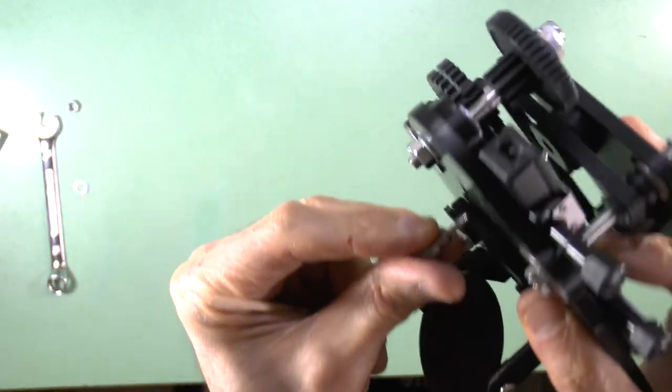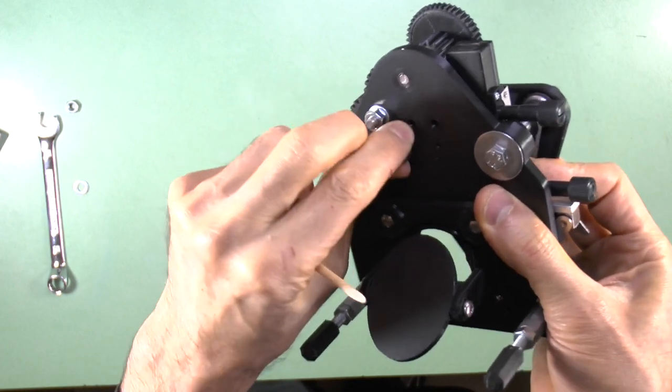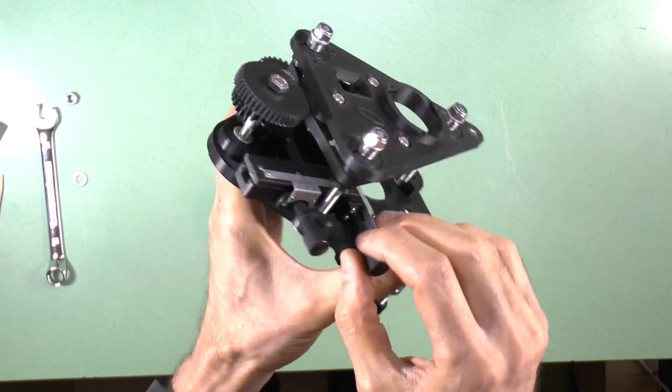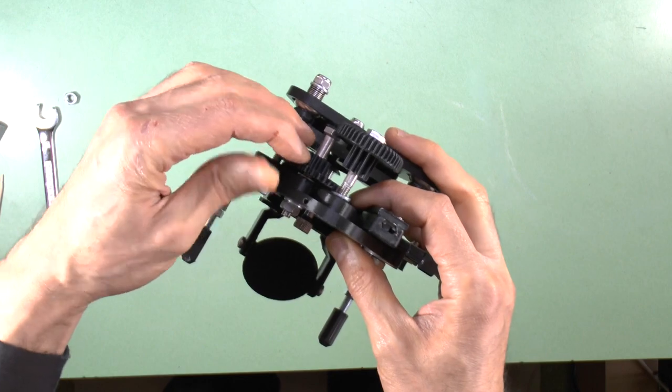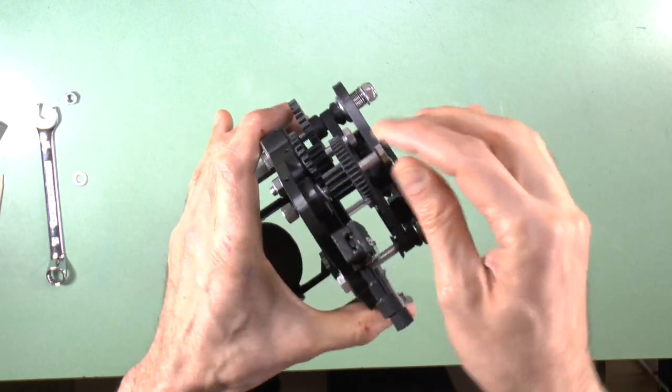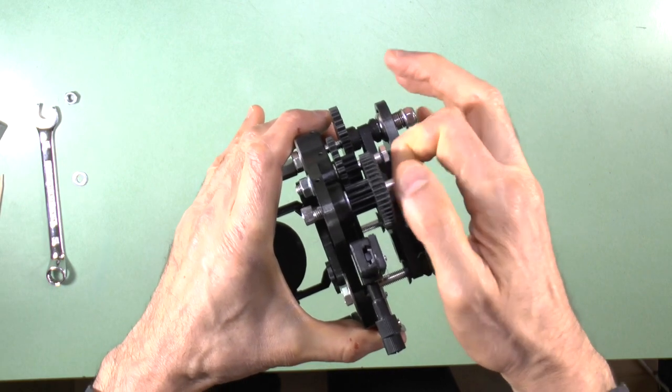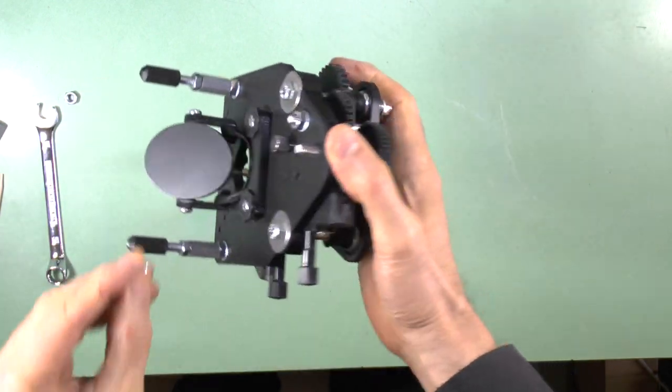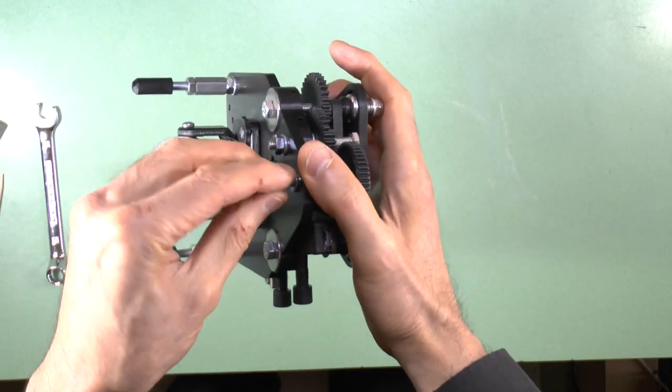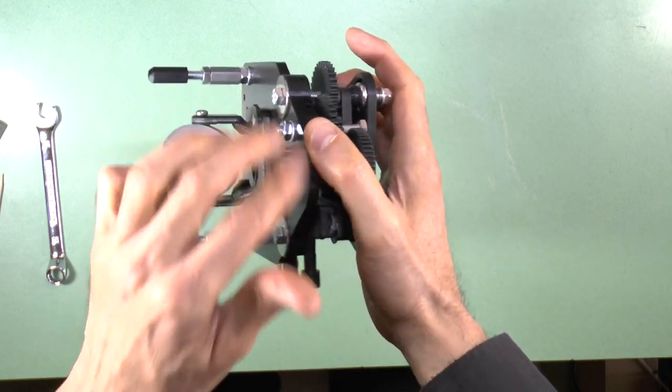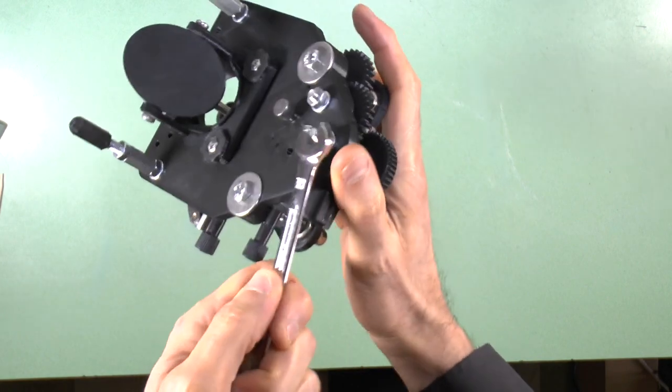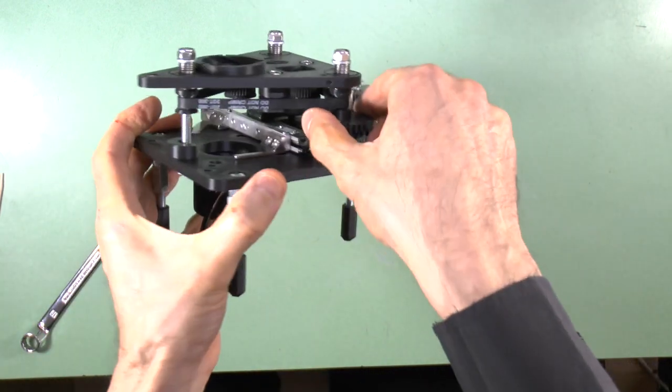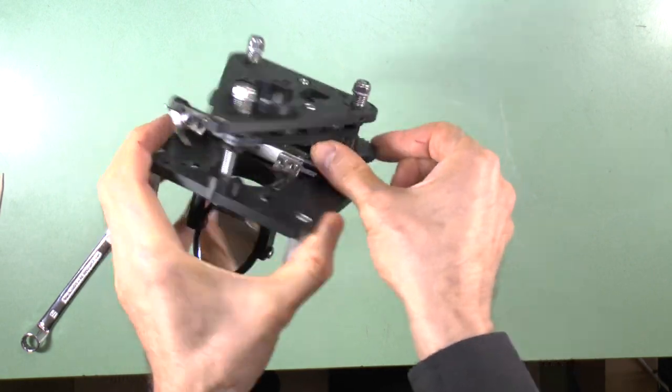Fix the slide holder in place with its fixing screw inserted from the underside of the base plate and tighten it. If you're using the all-metal slide holder, or if you have no intention of fitting the XY stabilizer, you can now lower the intermediate gear back down and retighten the fine gear post back to its normal position. Then reattach the rear washer and nut and leg on the underside of the base plate, and lower the stage back to a normal use position. If there was a PTFE ferrule on the top of the fine gear, reattach it now.